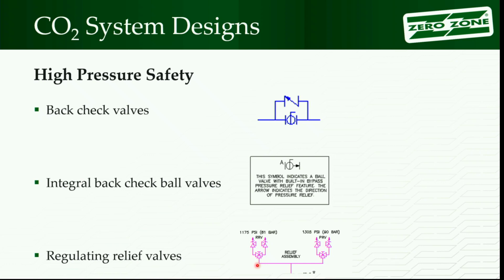And it's the same for all the valves and all the systems you have today. But odds are, because usually an HFC system never releases, you never would have noticed that. You never would have had experience knowing you need to be on one side or the other. Let's say I've closed off the left-hand side, I'm on the right-hand side. The safety valve releases, gets some dirt underneath, it's leaking. I can come back, switch the valve over, close off the right-hand side. The left-hand side is doing protection, and the right-hand side, isolated from the system, can be removed and replaced. So when you have the three-way valves, it's one or the other. Don't leave it in a midpoint position. That way it gives you a chance to service it if you need to down the road.